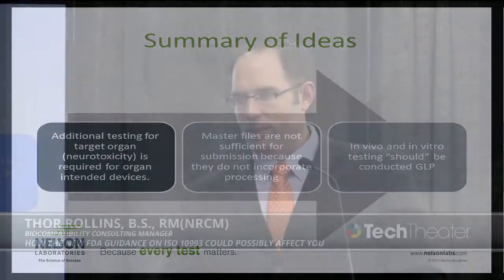The next one is kind of that thread again: master files are not sufficient for submission. We have people that say, hey, my NuSil silicones has a master file with the FDA, so I don't have to do any biocomp. If it has a master file, that's great. We can use that, but once again, you're doing processes to it, you're doing sterilization to it.